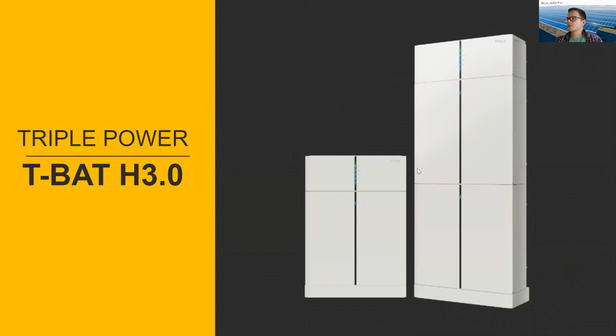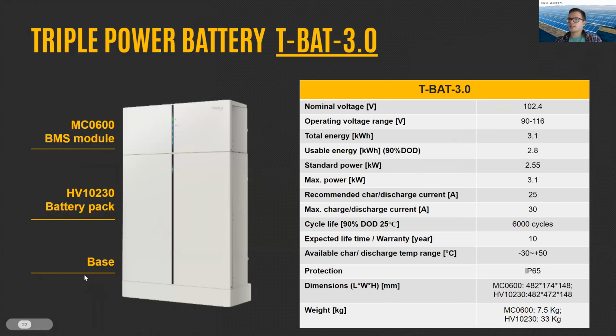So what does the system consist of? It consists of the base, which comes with the BMS module. The base we use just to level the system, because not always, on a construction site, sorry, do you have a leveled floor. On top, you put the battery pack, and on top of that, you put the BMS module. BMS means battery management system, which ensures the communication of the battery pack with the inverter.